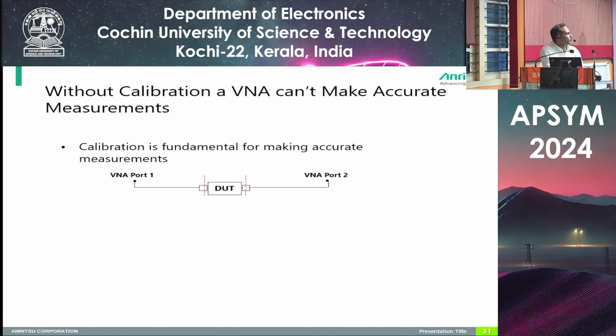So why do you want to do the calibration? Because whatever the DUT measurement is, we are measuring only the DUT. We are not interested in the cable loss or the instrument error that will be there in the instrument or a cable. So to concentrate on taking only the measurement of the DUT, we have to do the calibration at the end of the ports, and in parallel we will extend the reference plane up to the end of the connectors here. Okay. So it will give only the information of the DUT once you have done the calibration.